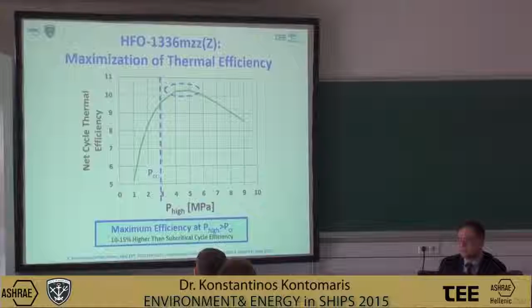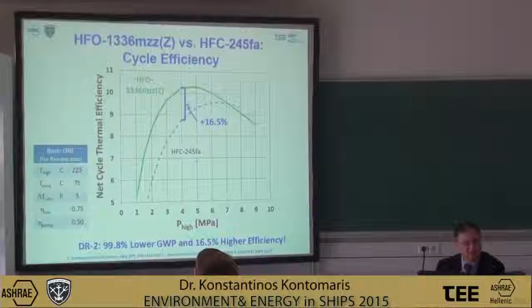And here is how the efficiency of power generation with the new fluid compares with the incumbent fluid. You can see, at least up to the sensible pressures that would be practical, the new fluid achieves significantly higher efficiencies than the currently available fluid, above 16% higher. So you accomplish a reduction of 99.8% in GWP, and at the same time you accomplish a 16% increase in efficiency. So that makes the new fluid pretty attractive. And in the last 2 minutes that I have left, I will mention another potential application using again the new refrigerant.